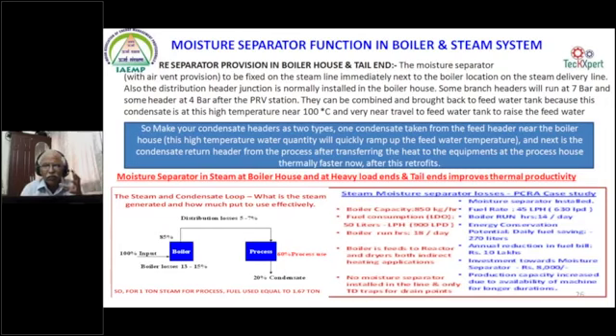Whatever condensate is taken from the boiler house after the moisture separator at the boiler house or at the distribution header will be very hot. It will have a higher amount of latent heat that can definitely increase your feed water tank temperature. Next stage is you bring down all your return temperature. See, the temperature to the process has gone to 90 degrees or 120 degrees, but when it is returning, it comes to only 60 degrees.